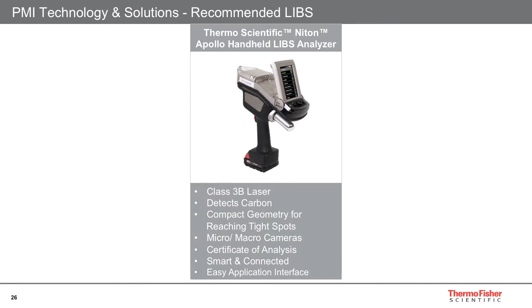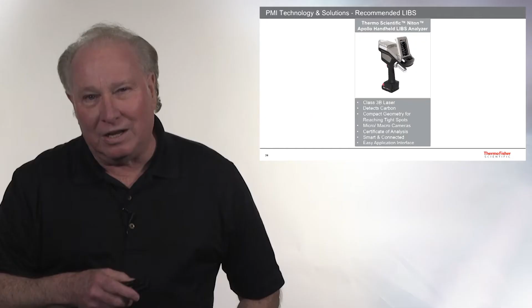One nice thing about this, Thermo Fisher Scientific makes a good LIBS device. It's unbelievable. They call it the Apollo. It's handheld. It is wonderful and it's recommended. It's a class 3B laser. It has the ability to detect carbon, and it can do low levels of carbon, and it depends on what you're doing. I'm doing carbon steel, a low alloy steel, I'm stainless steel. You still have to calibrate for all of that, and this can do a great job.